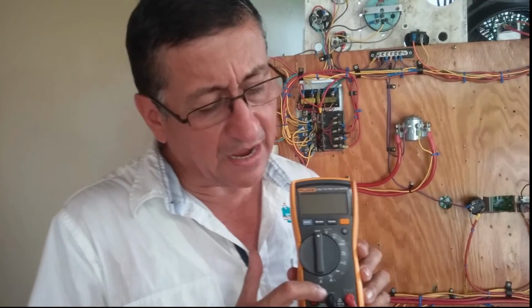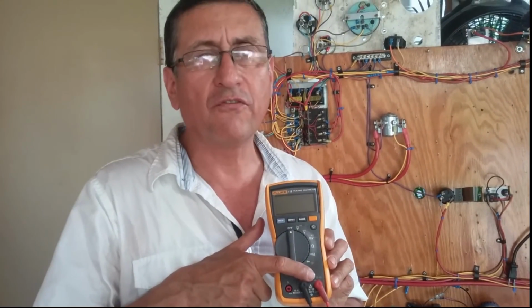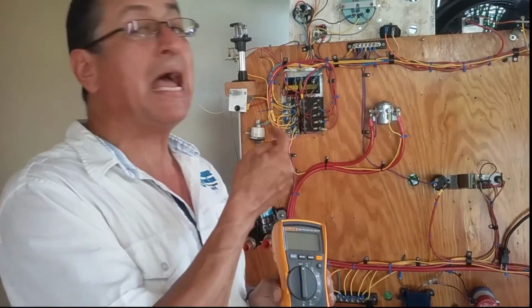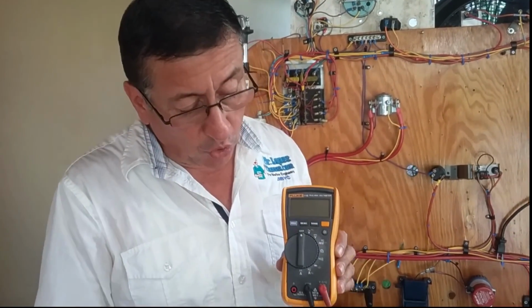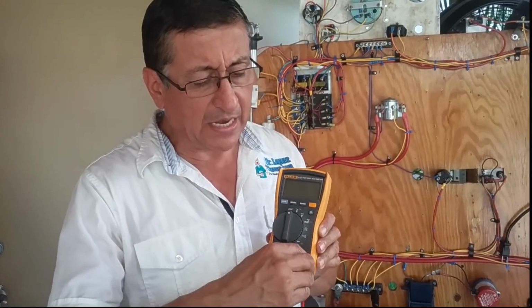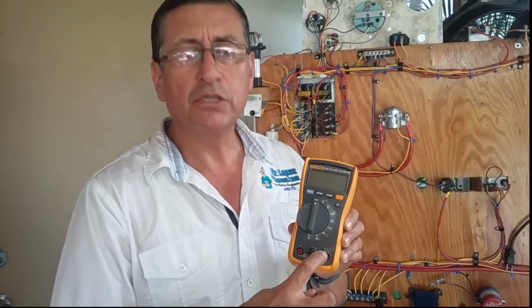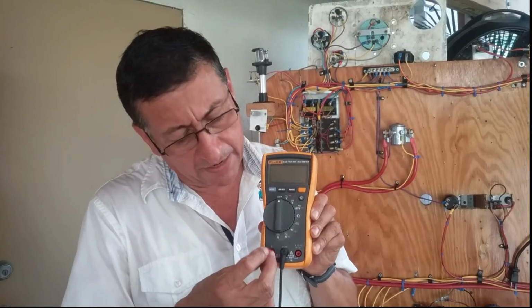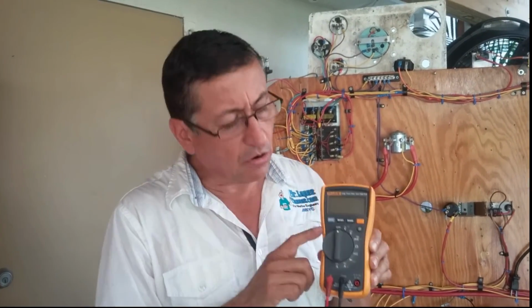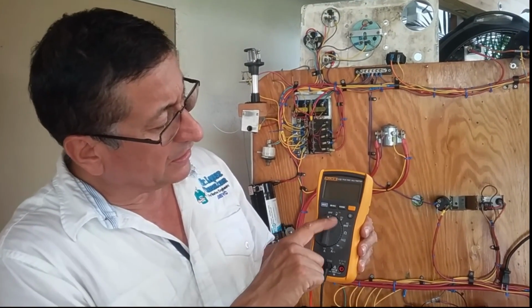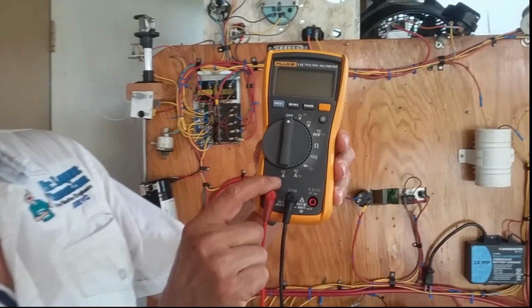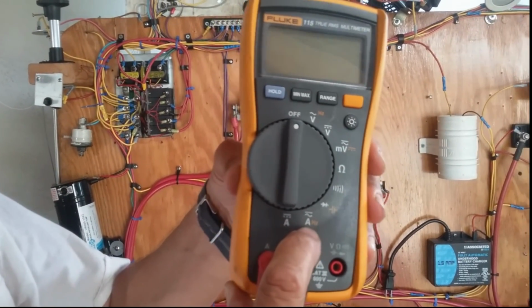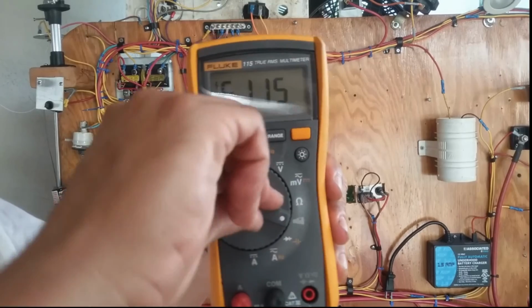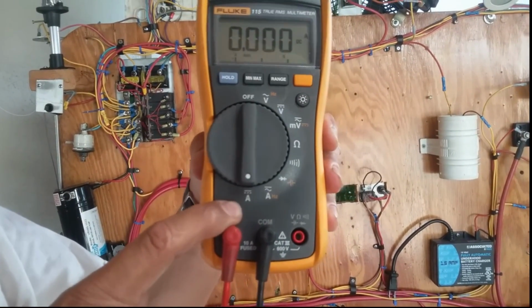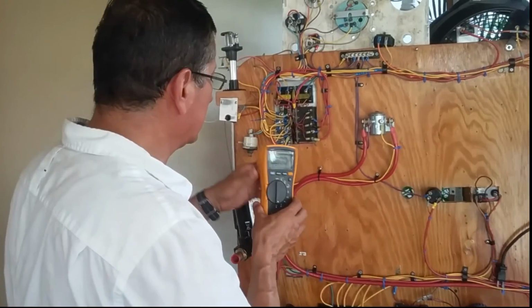All multimeters have a common connection, one connection for volts and another connection for amps. Because I want to read amps in this panel, I am going to connect my negative on the negative terminal and my positive not in volts. I am going to connect in amps. Alright, I connect in amps, and right now I am ready to select the function amps. You can read amps DC and amps AC. In this particular case, I am going to read amps DC. Okay, and this is the process.